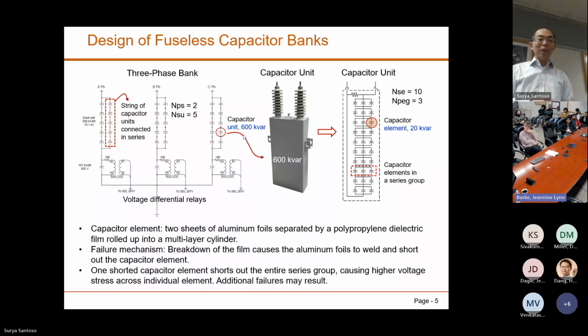Now what happens if there is a breakdown of the dielectric? Remember that the dielectric is in between the foils. If you have a dielectric breakdown, the 2 foils are going to weld, and they form a stable weld. So the impedance is going to be 0, because it's a fault. So if one capacitor element fails, it will take out the entire group. In this case, we are talking about a fuseless capacitor bank design.